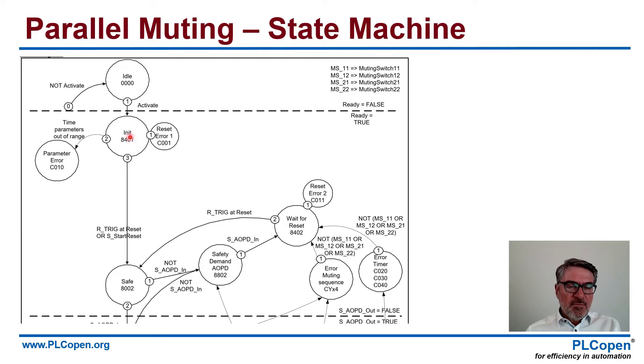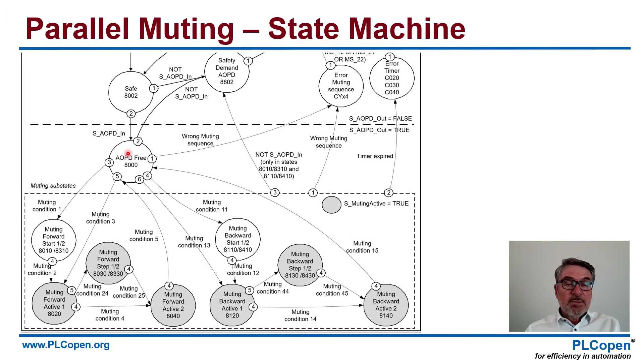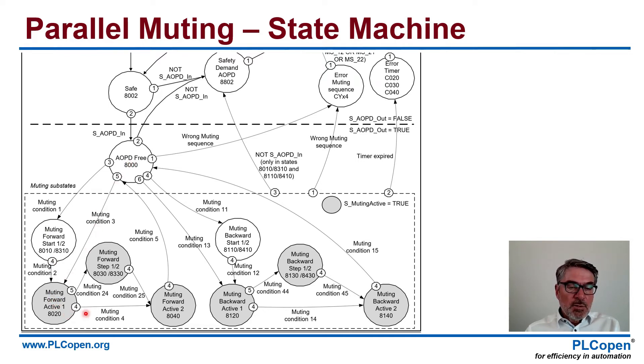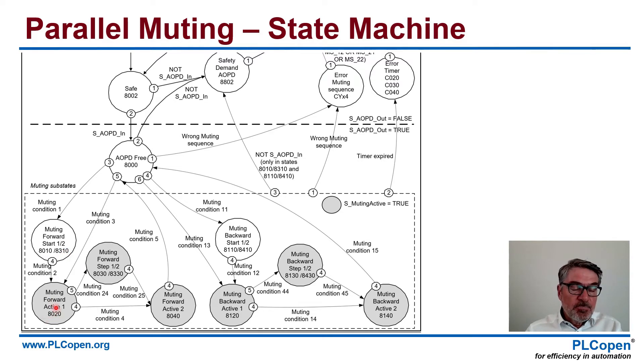If that's okay, and we get an R_TRIG at Reset or we have a start reset, we get to state 8002, which we call safe. For that, we have two ways out. One is the not AOPD — there is no safety demand — so we wait for that. And then we go down. There is a request; we move to the AOPD free, state 8000, the safe mode. Then we check the whole muting sequence. You see muting condition one, muting condition two, muting condition three — which goes directly — and muting condition four. Muting condition one moves to two bubbles — 8010 and 8310 — and you can come out of those to 8020. You go from 8010 to 8020, or from 8310 to 8020, under muting condition two.